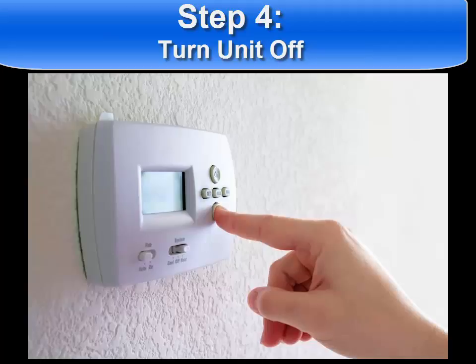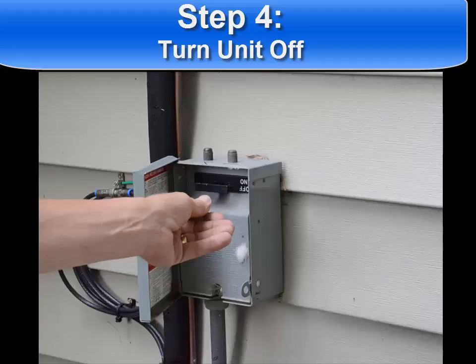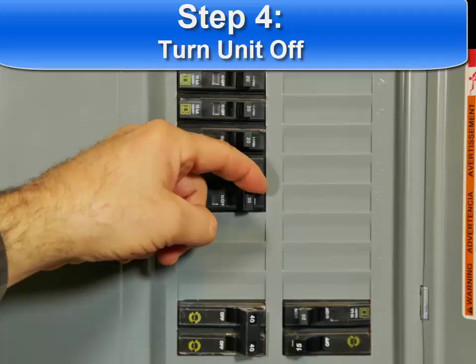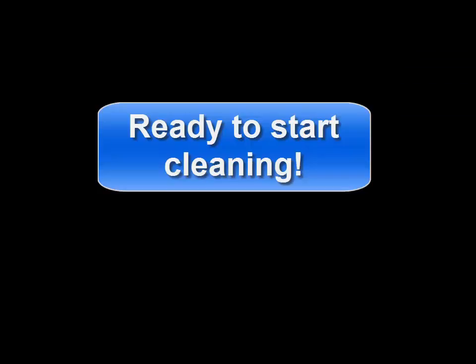Lastly, don't forget that you must turn the unit off before cleaning it. This doesn't mean simply that the unit isn't running, in other words, set to a higher temperature, but rather the unit should be turned off at the switch. Usually this is a separate 240 volt power box near the unit, or you can turn it off at the circuit breaker box. With these things addressed, you're ready to start cleaning the coils.